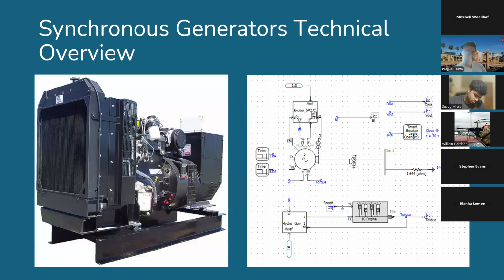Unlike large power plants that benefit from the stability and inertia provided by multiple interconnected generators, microgrids often rely on one or a few generators to maintain voltage and frequency. As a result, each generator must operate within very tight tolerances, with its rotor speed precisely matching the system's required synchronous speed. Load fluctuations in a microgrid can be significant, especially when renewable energy sources, such as our PV array, have differing power supplies. Any deviation from these parameters can lead to voltage fluctuations and unstable power quality.